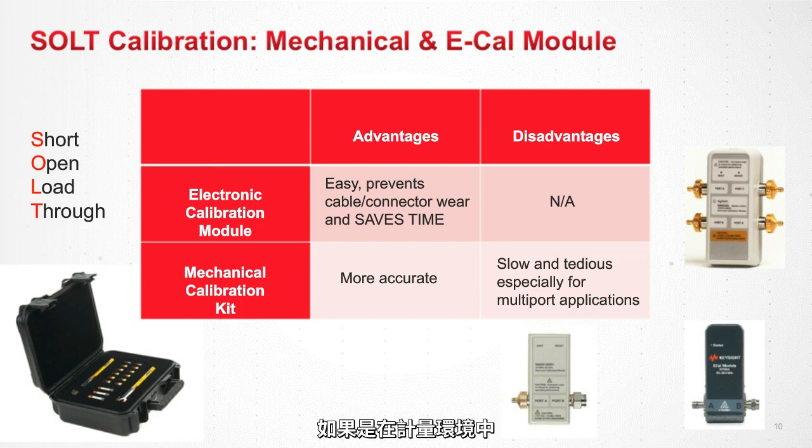If you're in a metrology environment where you have a lot of time in R&D and you've only got a mechanical cal kit, use it. That's not a problem. But practicality, in my experience, has shown that ECALs work very well, and I use them personally all the time myself.